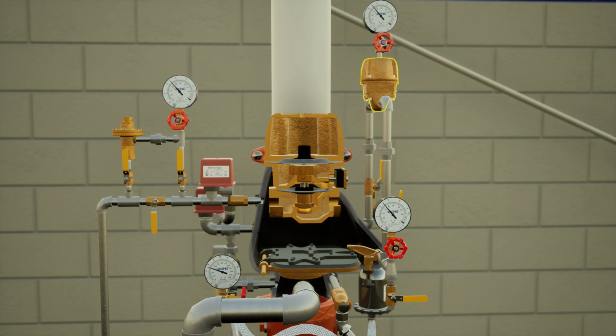In this scenario, we are looking at a warehouse protected with a VXR dry system equipped with an accelerator. The VXR is a differential drive valve that operates on a mechanical advantage with a 6-to-1 pressure differential. The valve features minimal moving parts and can be externally reset. An accelerator is a device that speeds up the process of tripping a dry system.